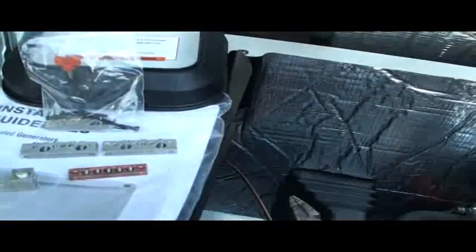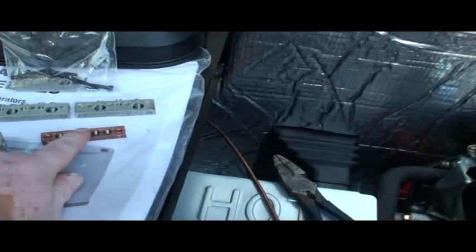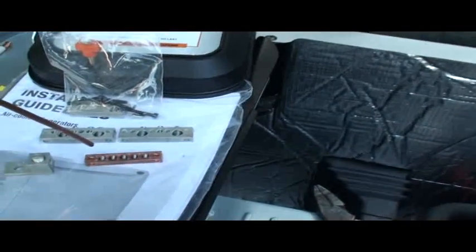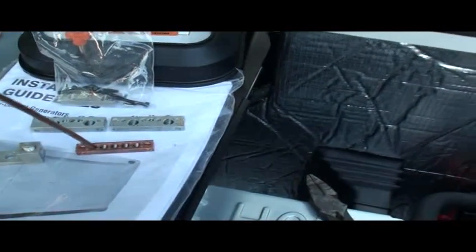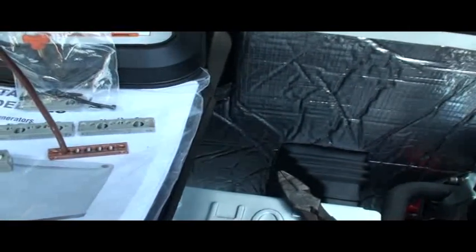As you can see right here, this is the factory ground bar, and here's a piece of number four solid. And if you put it right next to it, that will work. Number four solid will work in there.